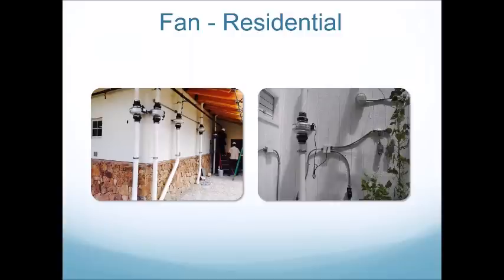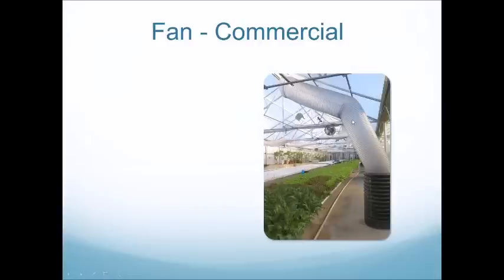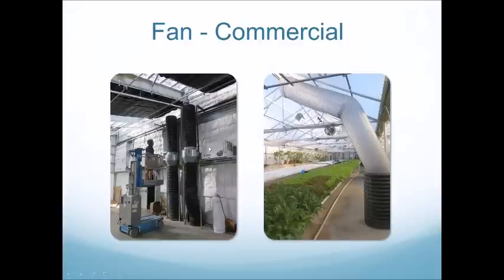The way we wire our thermostats and fans: we generally have thermostats hardwired to an outlet, which are connected to the fans. For commercial fans, these are 24-inch diameter fans rated at somewhere close to 5,000 CFM — much greater power than the smaller systems. This is a much larger greenhouse, with different complications in mounting the fans due to their weight and other variables.